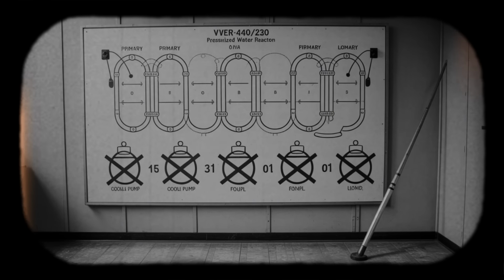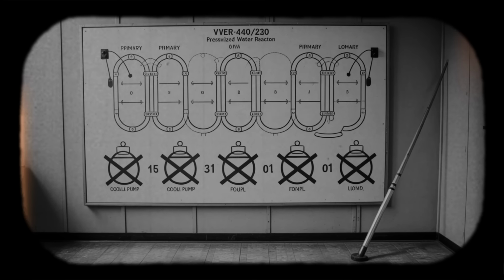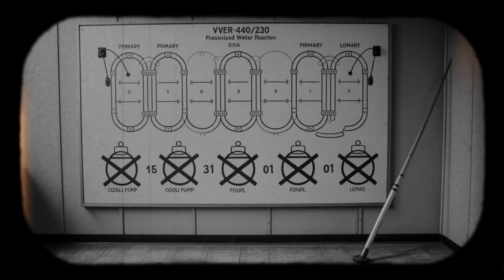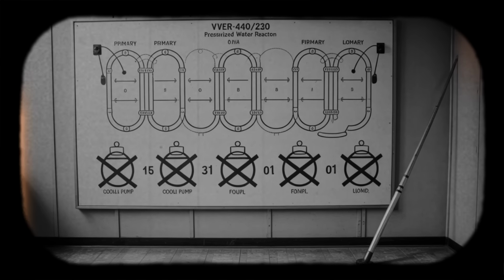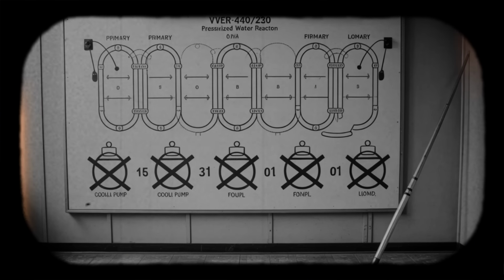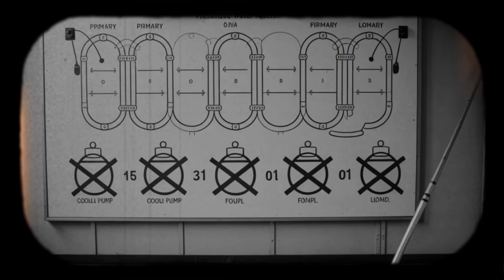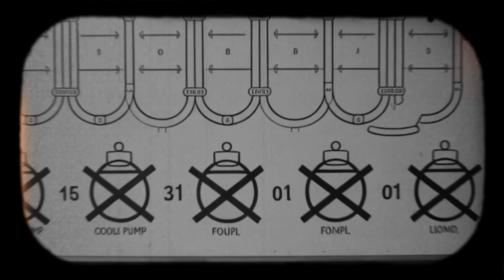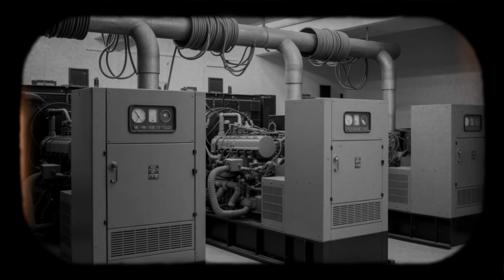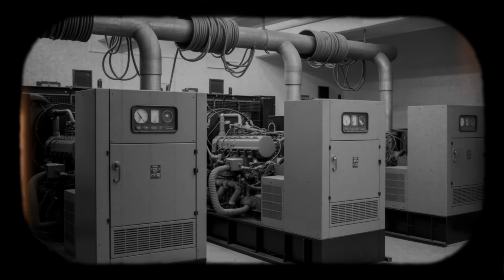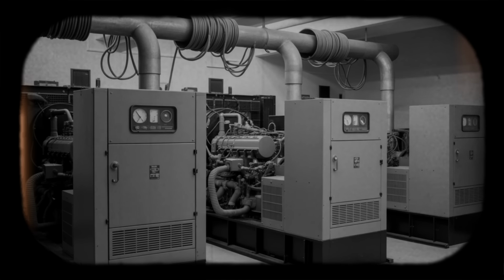Instead, the OECD review documented what happened next. The fire spread over the whole cable tray, also destroying other power and control cables. Cable insulation became fuel. Flames propagated along the tray, consuming not just the original 6 kV power cable, but also instrument cables, control circuits, and redundant safety train wiring that happened to share the same route. Design documents had treated these ducts as passive infrastructure. Conduits, not hazards. Physical separation existed in some areas, but the main cable route through the intermediate building combined multiple trains with minimal fire-resistant barriers.